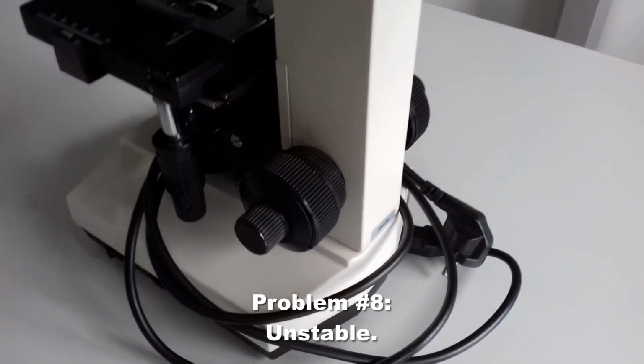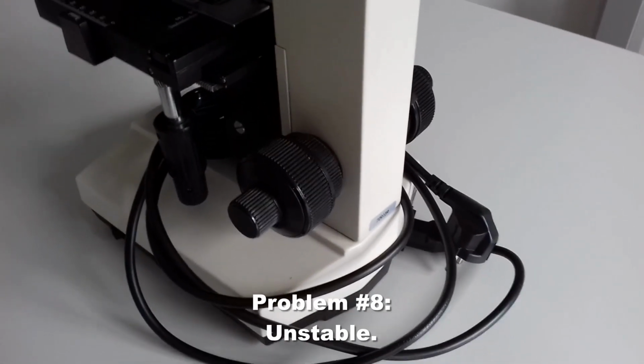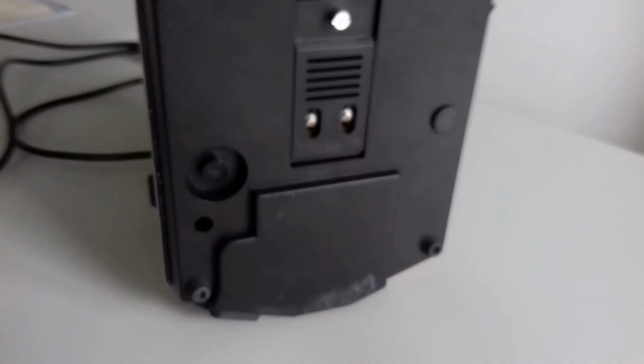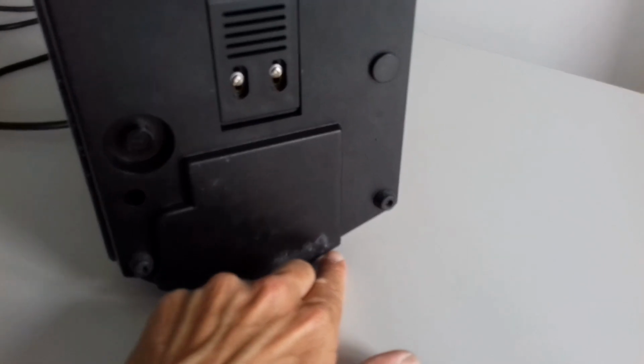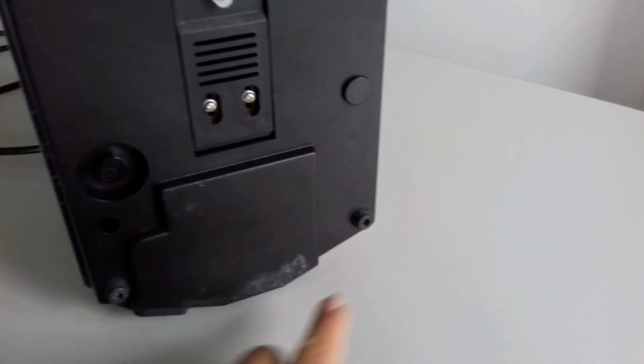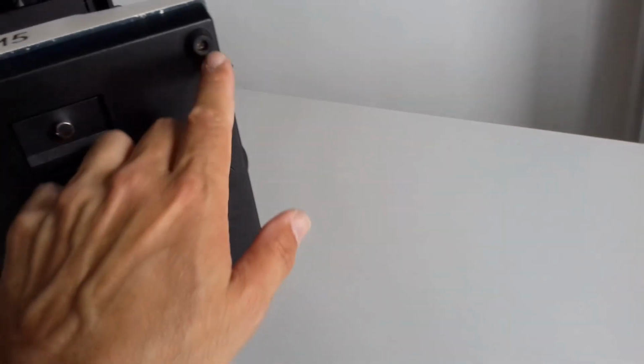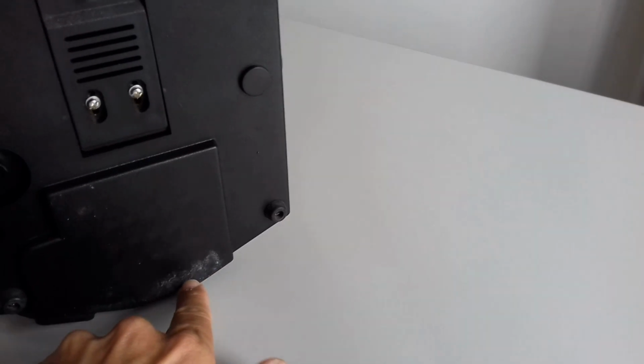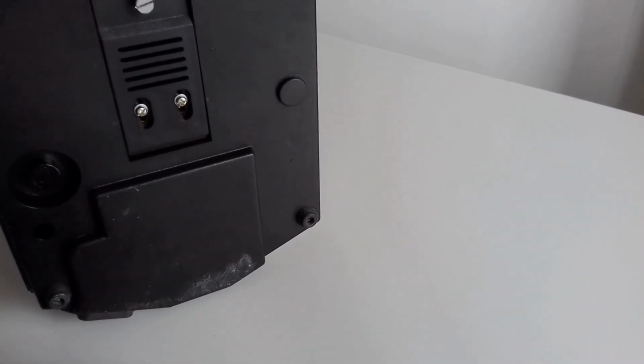Now this one is also quite an interesting one. All of the microscopes wobbled when they were on the table. I found the reason by flipping the microscope over. The cover on the bottom side of the microscope was too high, so the microscope was not standing on the four legs alone, but also on the microscope cover. You can see it here, where the dirt and dust collected. And I think this is not only a stability problem, but also an overheating problem, because beneath the microscope cover there is the transformer, because this is a halogen microscope. So there is not enough air between the microscope and the table, and this is in my view a design problem. This shouldn't be. The legs are simply not tall enough.